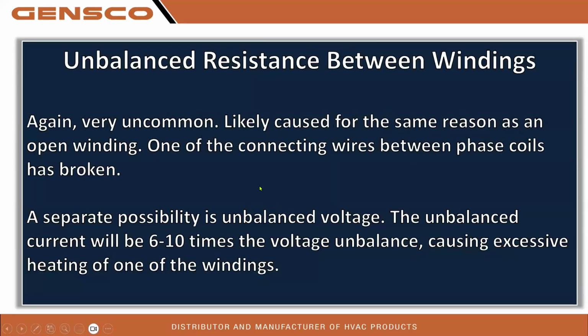An unbalanced resistance between the windings. Again, this is going to be very uncommon. It's likely caused for the same reason as an open winding. One of those connecting wires between the phase coils has broken, and now when we measure resistance, we're only reading 2 of the windings, 2 of the coils instead of 3, or 1 instead of 3. A separate possibility could be unbalanced voltage. The unbalanced current will be 6 to 10 times higher than the voltage unbalance, and this could cause excessive heating of one of the windings, which could alter its resistance.